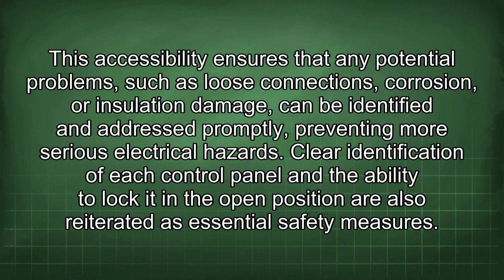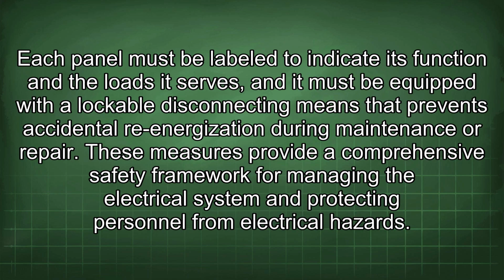Clear identification of each control panel and the ability to lock it in the open position are also reiterated as essential safety measures. Each panel must be labeled to indicate its function and the loads it serves, and it must be equipped with a lockable disconnecting means that prevents accidental re-energization during maintenance or repair. These measures provide a comprehensive safety framework for managing the electrical system and protecting personnel from electrical hazards.